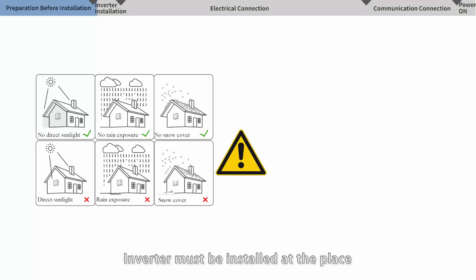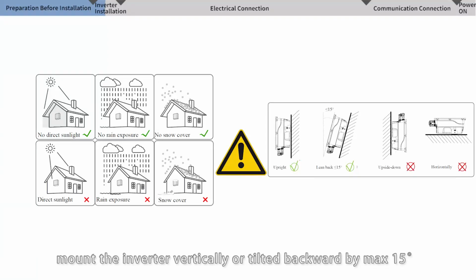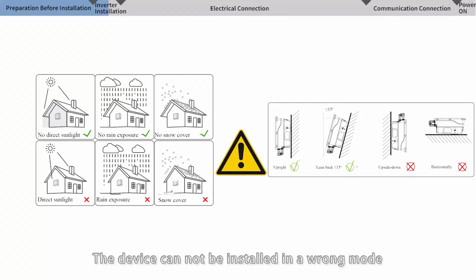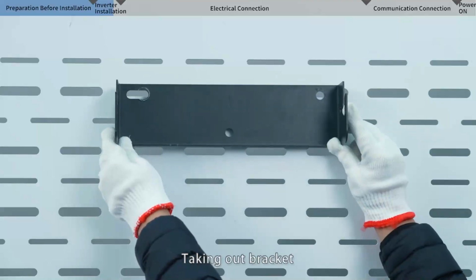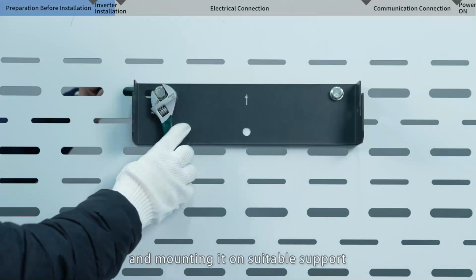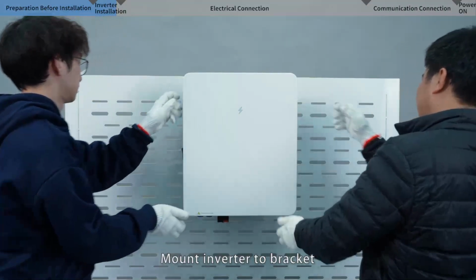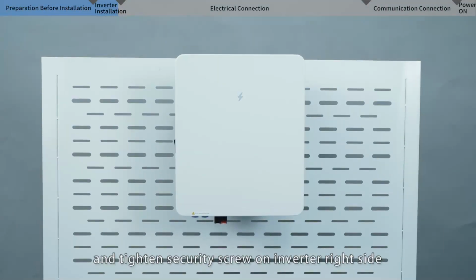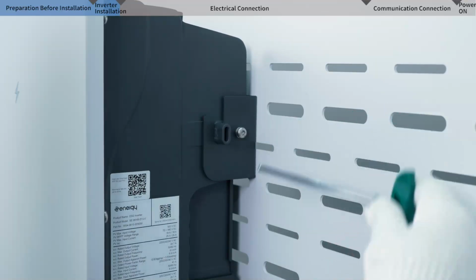The inverter must be installed in a place free from direct exposure to sunlight, rain, and snow, with enough space and good cooling conditions to ensure performance and a longer lifetime. Mount the inverter vertically or tilted backward by a maximum of 15 degrees. The device cannot be installed in a wrong mode, and the connection area must point downward. Take out the bracket and mount it on a suitable support. Mount the inverter to the bracket and tighten the security screw on the inverter's right side.